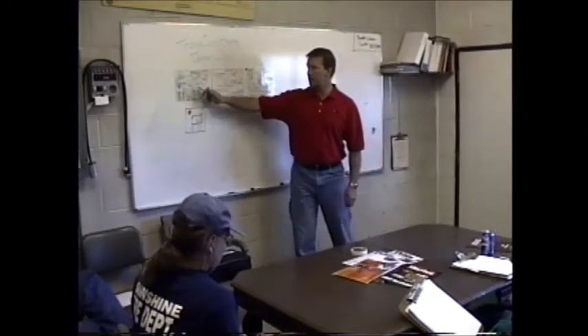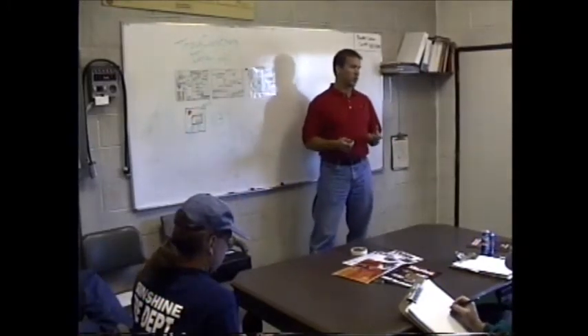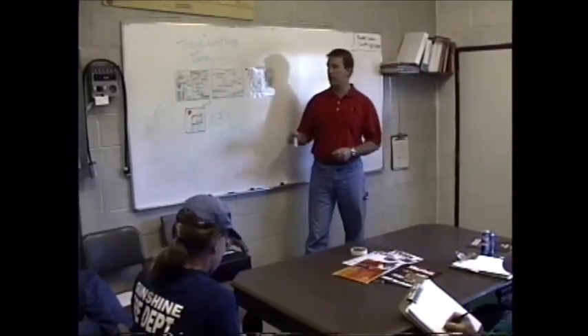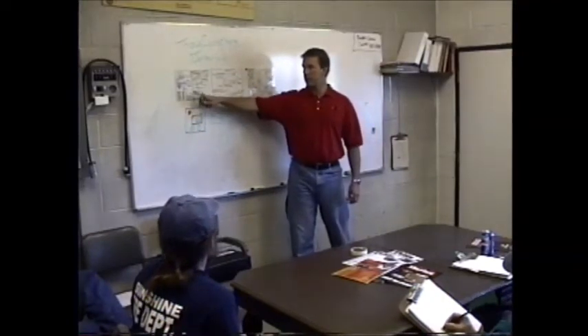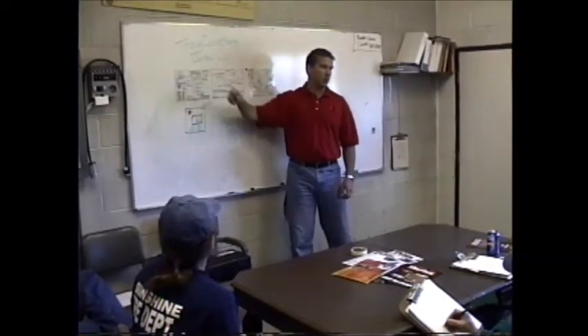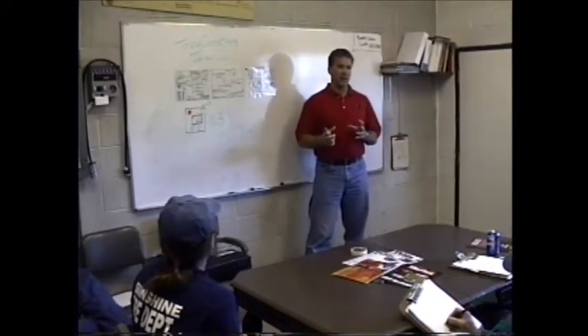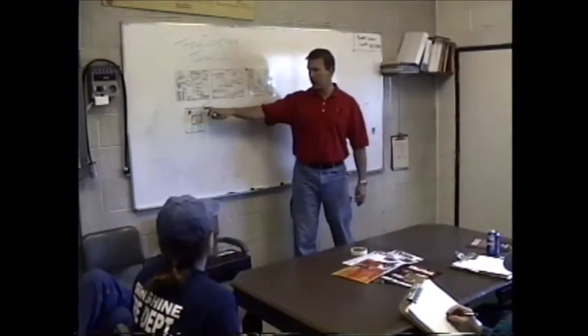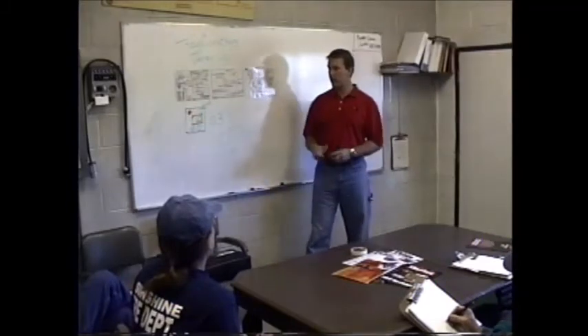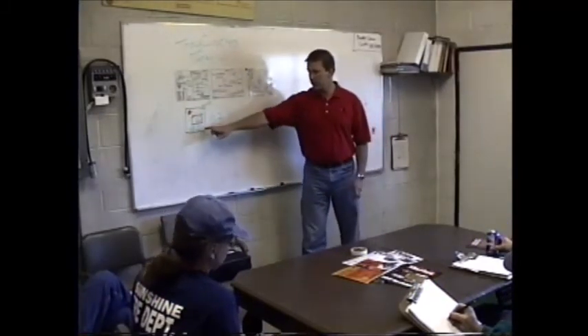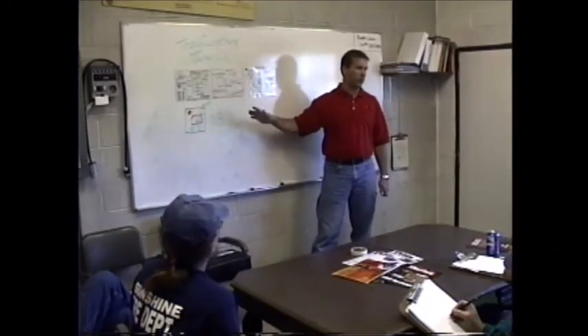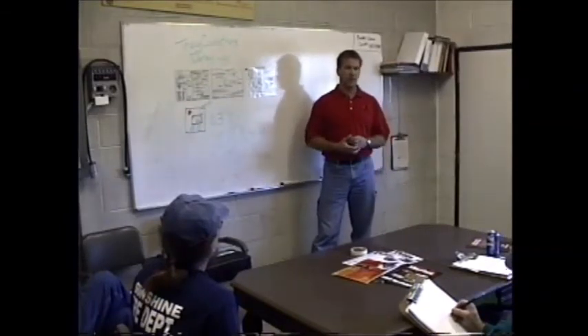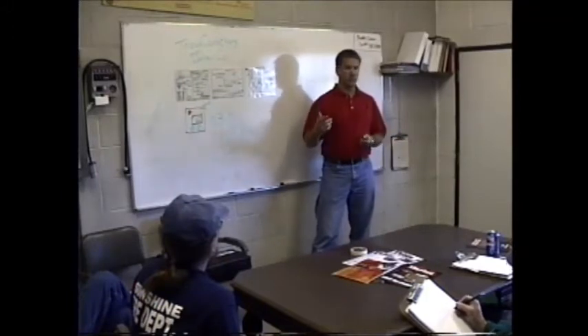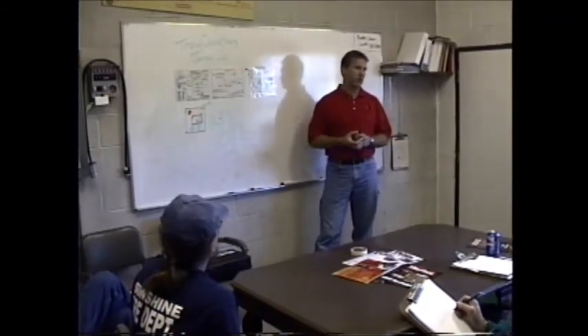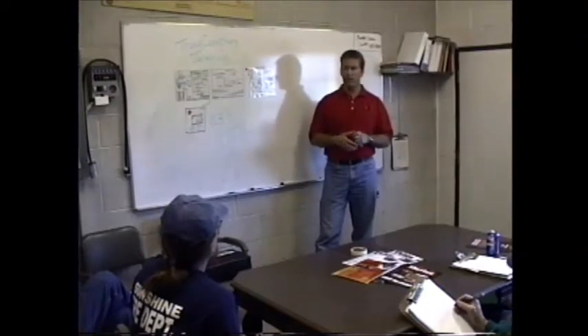But all of these lines are going to have the same foam percentage. One question that some people come up with is, is there any way I can make a 0.5% mixture on this line and a 1.0% mixture on that line? That's not possible. There's one metering valve, and that's here in this digital display, and it's always going to come up at 0.3. Even if you push this arrow 10 times and move it up to 1.3 for whatever reason for that scenario, if you shut the master switch off in the truck and go out for your next call, it's still going to default back to 0.3. So you don't have to worry about changing it back every time.